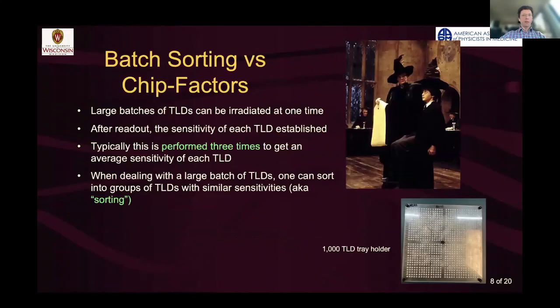When you choose to use TLDs, you can either keep track of their individual sensitivities, or you can use what's called batch sorting. And that's when you take a very large batch of TLDs. On the bottom right, there's a photograph of a holder that holds 1,000 TLDs. And we could take that holder in front of a cobalt-60 source or cesium source or whatever and irradiate all of them at once. And then after they're all irradiated, you read them out and you get a sensitivity. We typically like to perform this 3 times to get an average sensitivity of each TLD. And then what you can do is bin those sensitivities into bins that are about 1.5% in agreement with each other. And then you have a whole group, and it's called sorting TLD.